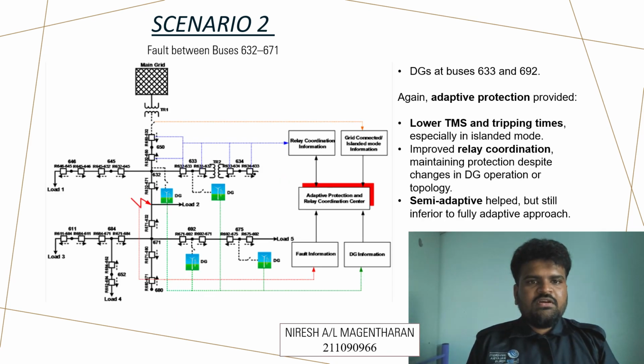Scenario 2, fault between buses 632 to 671. DGs at buses 633 and 692. Again, adaptive protection provided lower TMS and tripping times, especially in islanded mode, improved relay coordination, maintaining protection despite changes in DG operation or topology. Semi-adaptive helped, but still inferior to fully adaptive approach.